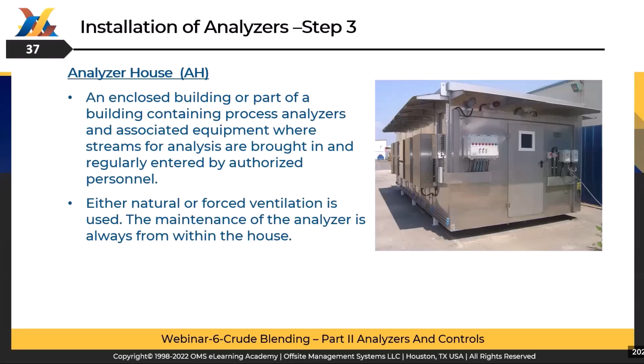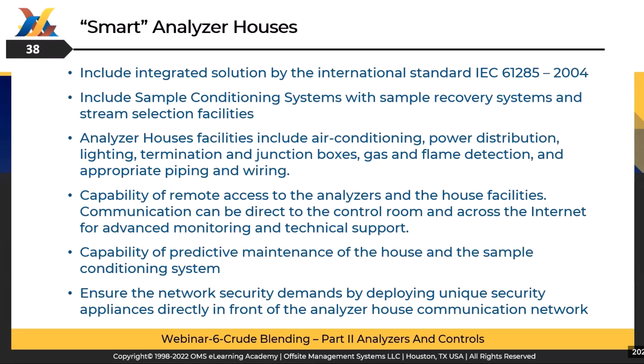Okay. So the so-called smart analyzer house is actually an effective solution for integrated scope. These solutions are mainly designed based on the international standard IEC 61285. This house typically includes a sample conditioning system with sample recovery, stream selection facilities, air conditioning, power distribution, lighting, termination and junction boxes. It also includes gas and flame detectors inside the house. The trend over the past years is toward remote access to the analyzers and house facilities. It means that there is no need for a physical presence at the analyzer house, and all the work can be done remotely. Next slide, please.